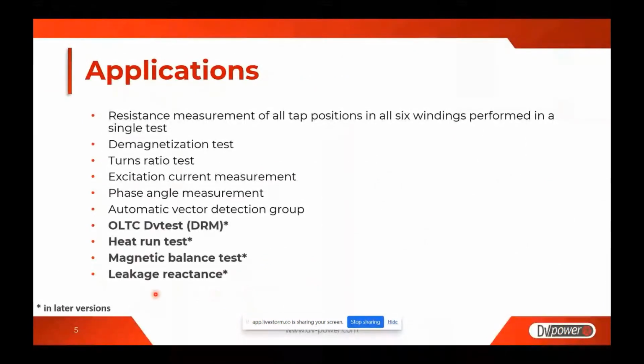And here you can see a list of applications. So pretty much you had a chance to see and experience this with our previous solutions with TWA and TRT series. So resistance measurement of all tap positions and in all 6 windings performed in a single test. Again, with our new device, you will be able to demagnetize the core after the winding resistance measurement, turn ratio tests, and excitation current measurement also available.